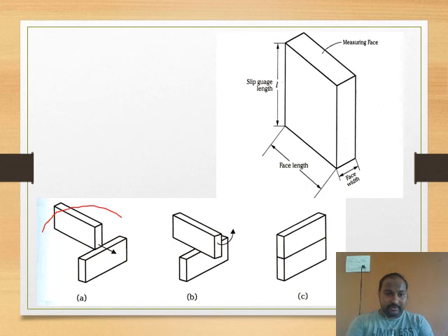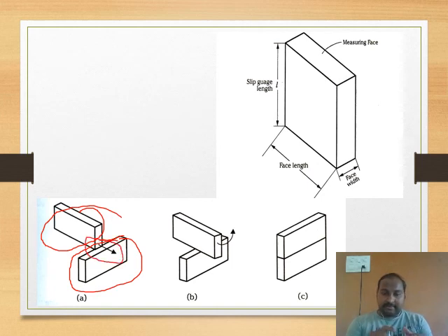First we have to keep one slip gauge perpendicular to the other slip gauge, and then we have to rub them in a perpendicular direction. Once they are rubbed and ensured that they are attached to each other due to molecular adhesion, then they need to be twisted. Once twisted and made parallel, with the two parallel surfaces in complete contact, that is the wringing process.